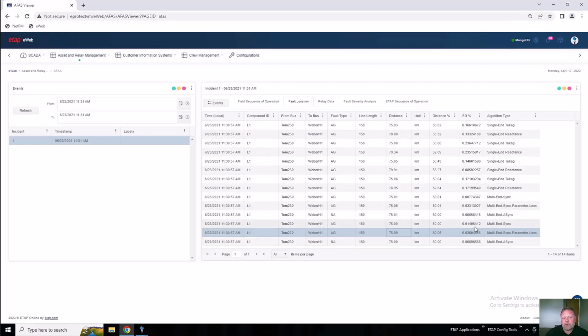So this reflects back to what I mentioned earlier about protection relays which provide a fault distance. This is only using the single-ended calculation, so it is not going to be nearly as accurate as the multi-ended calculations that we have here, where we can take in the disturbance records from both relays on each side of the line. In addition to the distance, we provide the distance percentage, which gives you a different way of seeing that information, and as I mentioned earlier, the standard deviation.